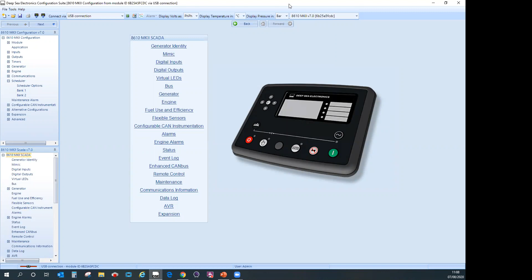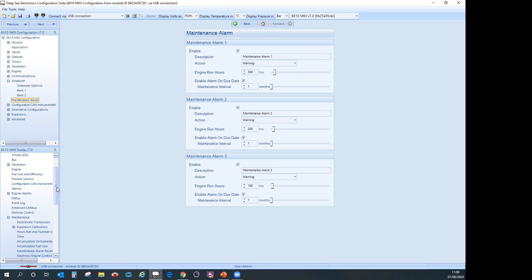So another good example where you might use SCADA, if we click on maintenance and then maintenance alarm reset, it's quite common for customers to have a maintenance alarm on their controller. So you'd configure your maintenance alarm in here. This is where you make your changes to your maintenance alarm. So every 300 hours, a maintenance alarm is going to pop up. It's going to give me a warning, or it might come on a date as well. So it's going to enable from one month from the date that this alarm's been set. If you're going to maintenance alarm, someone might go on site and they might want to reset the alarm. Perhaps they've done a service on it, or they've gone to check everything over. Then they're going to want to reset the alarm.